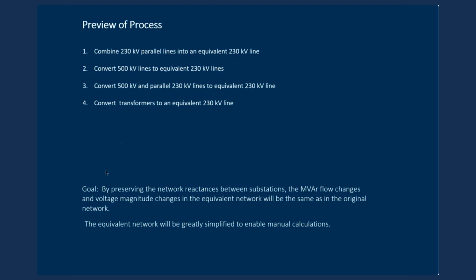Here's a preview of the process. For all the cases where we have parallel lines, we'll convert them to an equivalent single line with a smaller length. We'll also convert the 500 kV lines to equivalent lines with a much reduced length. We'll then also convert a case where we may have a 500 kV line in parallel to a 230 kV line to an equivalent 230 kV line. And finally, we'll convert the transformers, both the bulk power step-down transformers from 500 to 230 kV and generator step-up transformers to equivalent 230 kV lines.